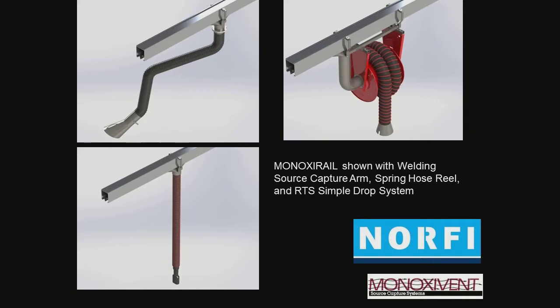And then if we go back to the original picture, I'm going to give you kind of a basis of design. So let's say we're looking at an 8-bay car dealership. My first question, if I'm designing the system, is I'm going to ask my customer, what's the worst case scenario? How many cars will be running at the same time? And if it's an 8-bay system, it's never 100%. Normally it's maybe 3, maybe 4 vehicles running at the same time.